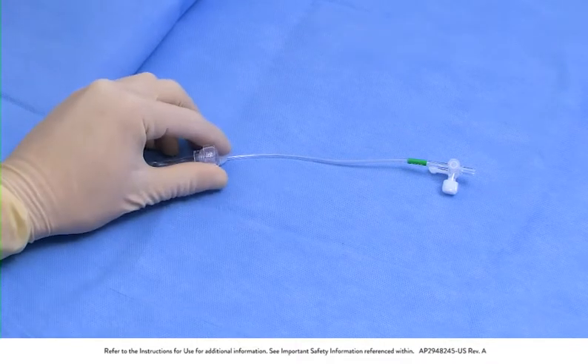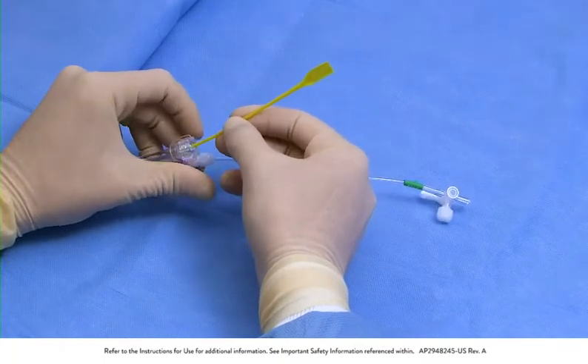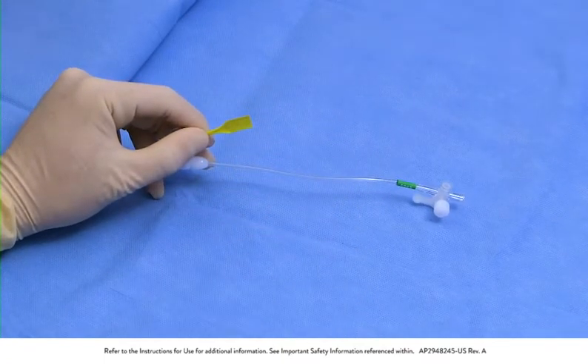Use the introducer tool provided to pass the loaded delivery catheter and bare wire through the hemostasis valve of the guide catheter or introducer sheath.